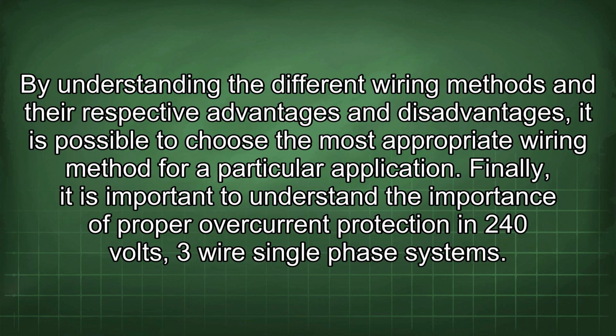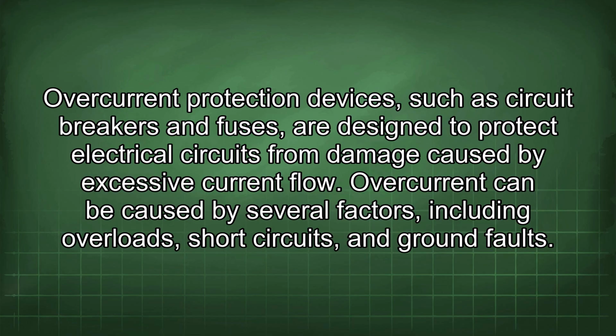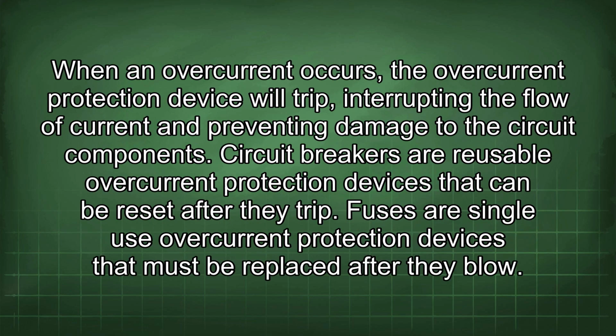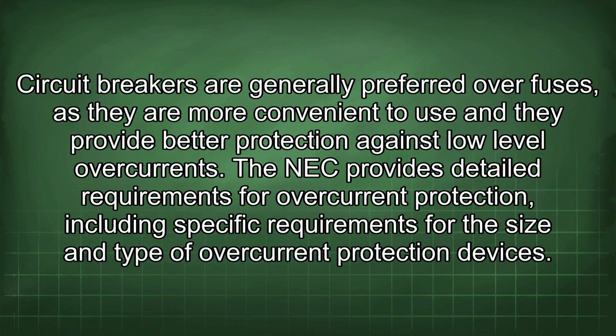Finally, it is important to understand the importance of proper overcurrent protection in 240 volts, 3-wire single-phase systems. Overcurrent protection devices, such as circuit breakers and fuses, are designed to protect electrical circuits from damage caused by excessive current flow. Overcurrent can be caused by several factors, including overloads, short circuits, and ground faults. When an overcurrent occurs, the overcurrent protection device will trip, interrupting the flow of current and preventing damage to the circuit components. Circuit breakers are reusable overcurrent protection devices that can be reset after they trip. Fuses are single-use overcurrent protection devices that must be replaced after they blow.